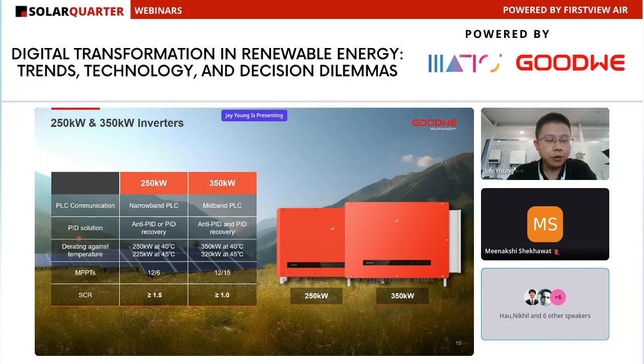And as for the PID solutions, for both inverters we have the two PID solutions. One is anti-PID, like PID prevention, and the other is PID recovery, like the PID repair function. For both inverters, we can guarantee that there will be no derating at 40 degrees. The MPPTs are different for the two inverters. And for the SCR, for the 350, we can ensure the minimum SCR is 1.0.